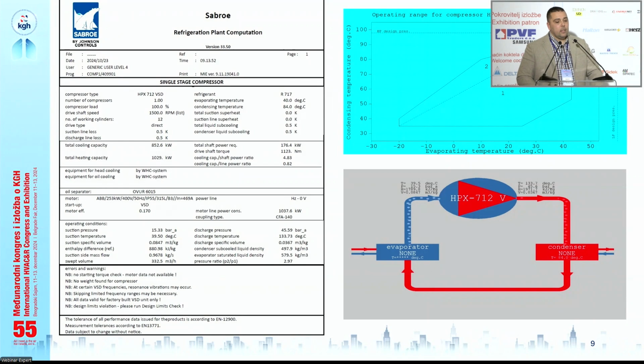On the right side here, we have the operating range for this compressor, and for our application, we see that it's in area 1, which means we will use just the standard oil cooling. And on the bottom, we have a simplified flow chart for this compressor, which shows us that on the discharge side, we have over 130 degrees Celsius of temperature and over 45 bars of operating pressure.